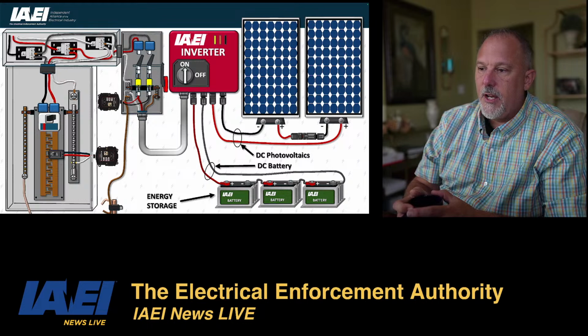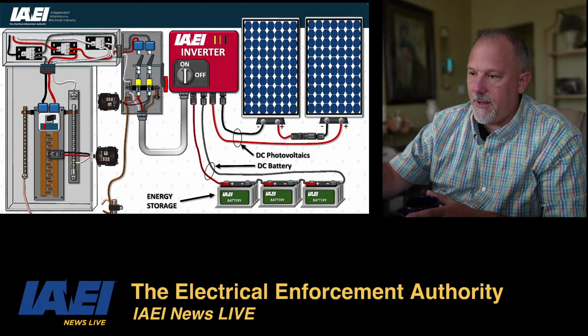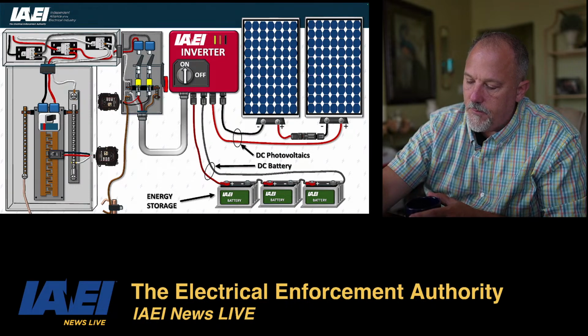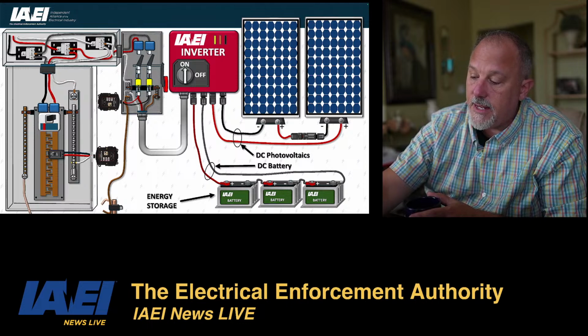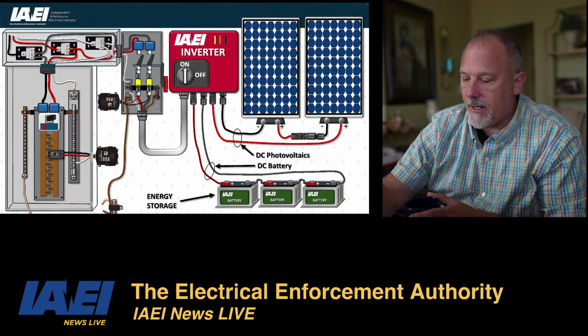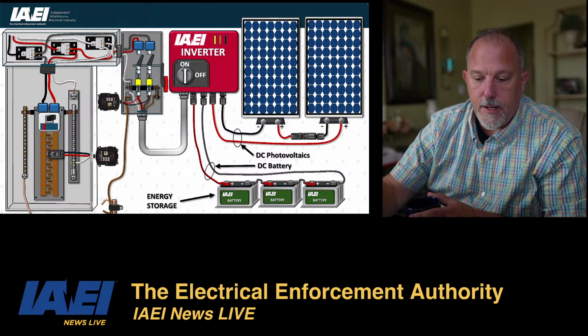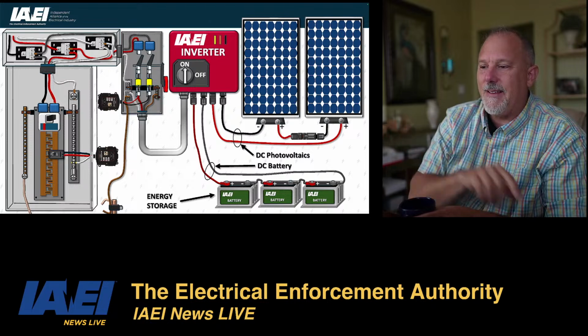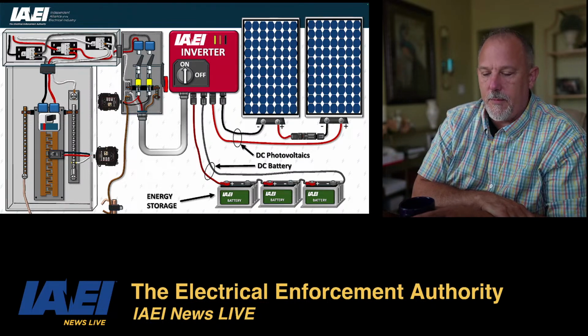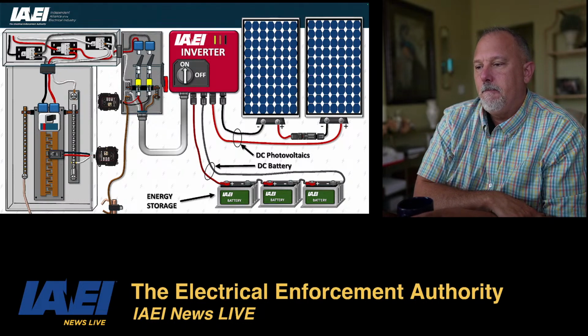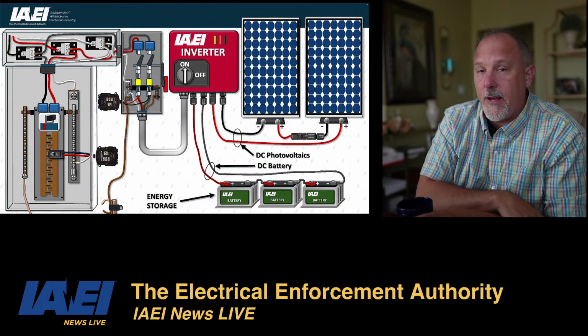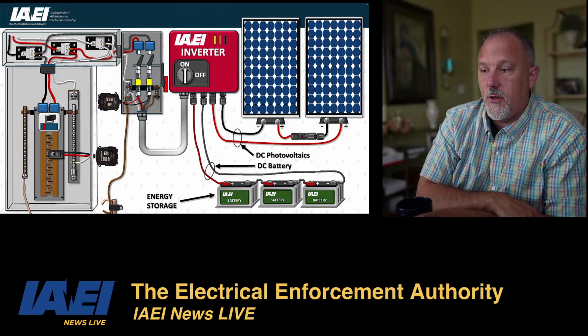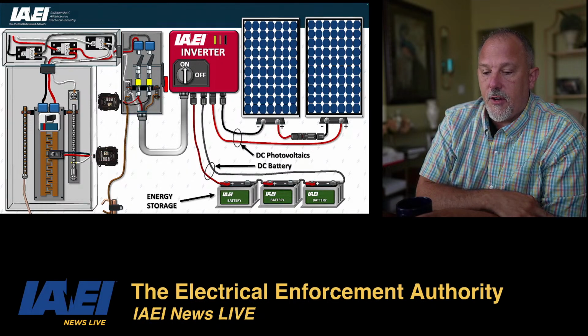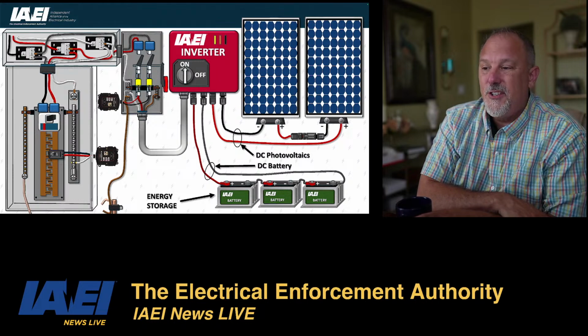Robert Osborne says only if that is rated for two conductors can you put two wires under the same lug. So I need to check that image to see if I can do that. Two grounding electrode conductors under the same, what would you call that connector? I don't know what you call that for a ground rod, for the grounding electrode. I drew that last minute. So, dual lug rated equipment. Kevin, thanks for chiming in. The important thing for that connection point for the grounding electrode conductor is that I'm going to have to pull the literature from those who make those connectors to see if a ground clamp can take two, or how you would connect two to that ground rod.